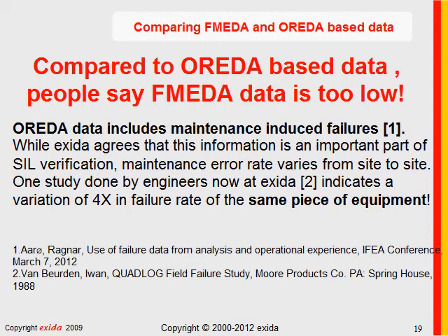especially when you understand that OREDA data includes maintenance-induced failures. I had a chance to visit Norway a few weeks ago and discuss these issues with people who were part of the OREDA analysis team. It was stated very clearly that maintenance-induced random failures are an important part of a safety performance-based verification system.